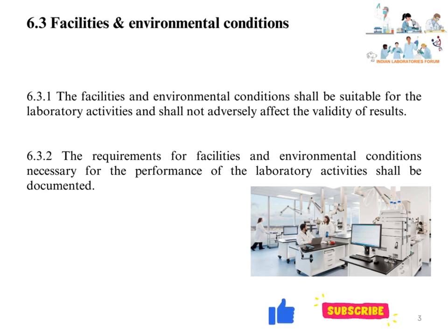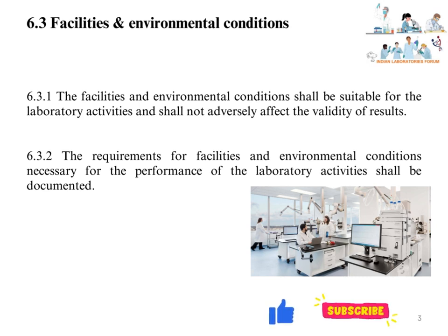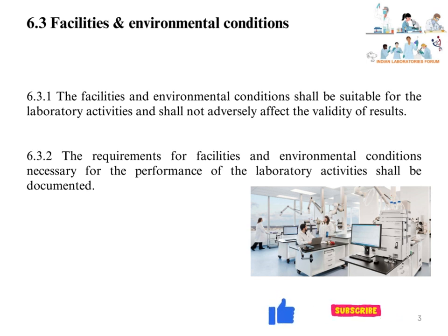The requirements for facilities and environmental conditions necessary for the performance of laboratory activities shall be documented. Laboratories should document what kind of facilities and environmental conditions are needed based on the type of testing conducted, which includes acceptance criteria for environmental conditions such as temperature limits, humidity limits, lux limits for lighting, pressure, vibration, electromagnetic disturbances, etc., based on type of testing.